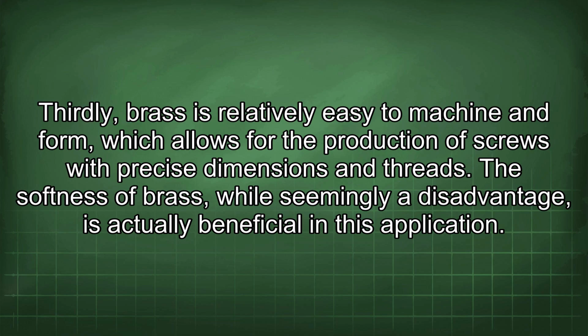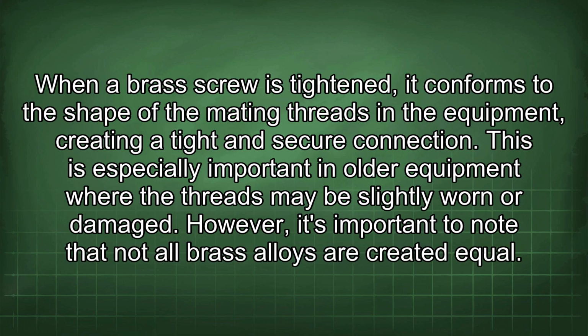Thirdly, brass is relatively easy to machine and form, which allows for the production of screws with precise dimensions and threads. The softness of brass, while seemingly a disadvantage, is actually beneficial in this application. When a brass screw is tightened, it conforms to the shape of the mating threads in the equipment, creating a tight and secure connection.